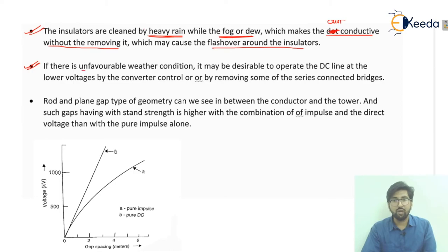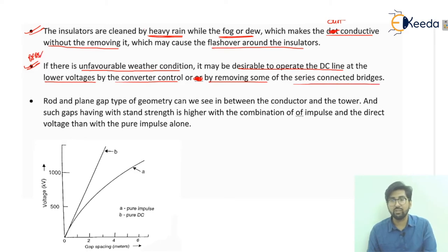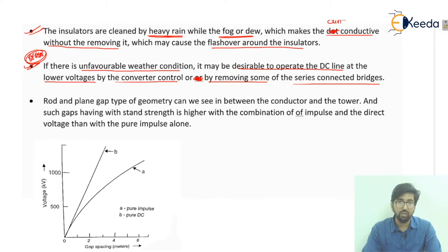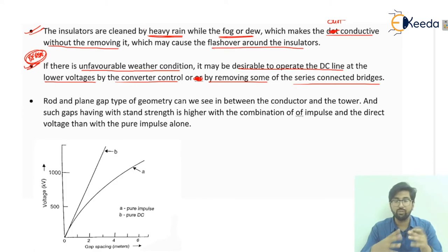Under unfavorable weather conditions, it may be desirable to operate the DC line at lower voltages — by converter control or by removing some of the series connected bridges — so that there will be no harm to the equipment.